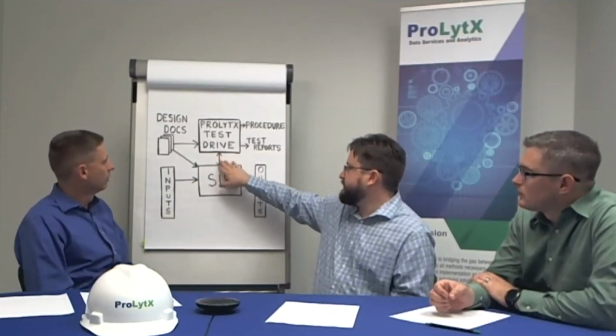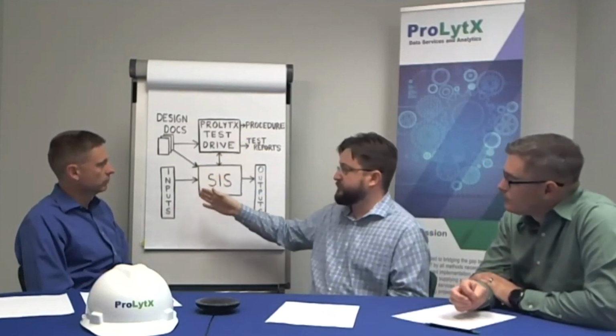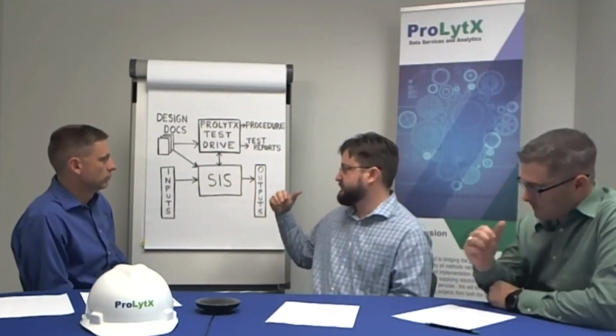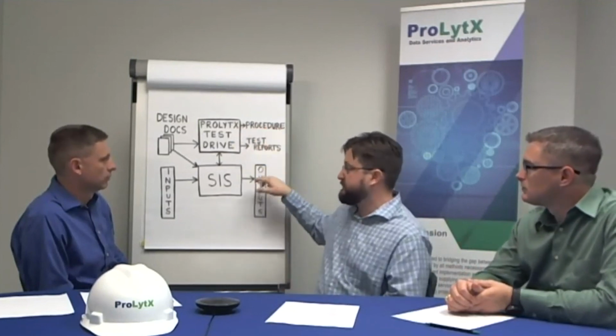That's right. We actively communicate two ways with the SIS. We write the test procedure such that the inputs are overridden and we force values in, and we're constantly monitoring all of the tags in the system. So we have expected results as you go through the procedure. Each step has actions and results. The software is constantly monitoring those, and when you execute a step, it can record whether it passed or failed with the timestamp, and every change that happened in the system as a result. All of that gets documented. We output that as a procedure, both before you run the test and after, with embedded test results and timestamp information. We also produce a full test report with an audit trail, a full log of everything that occurred while you ran that test.